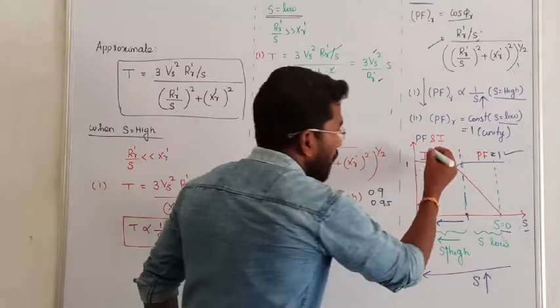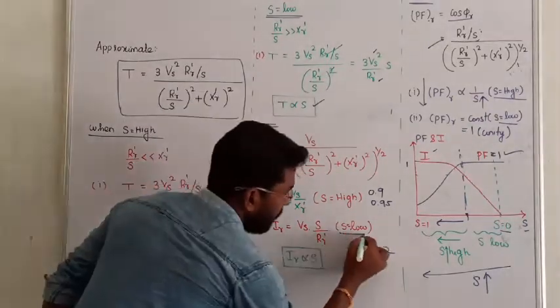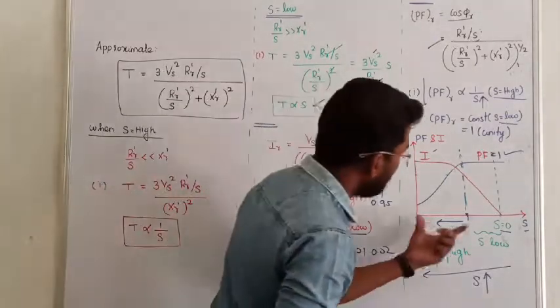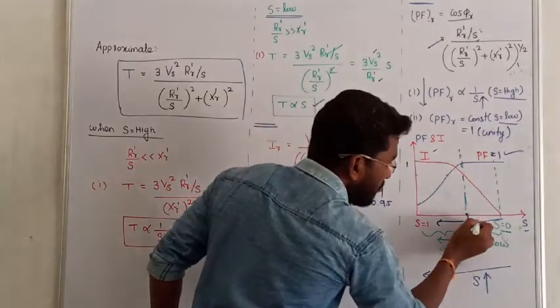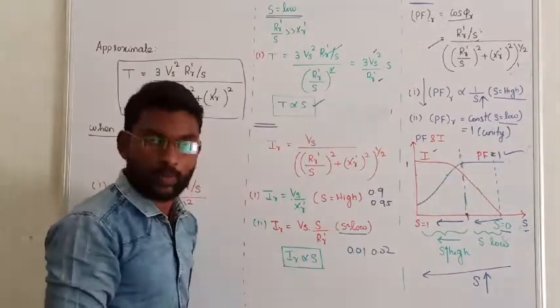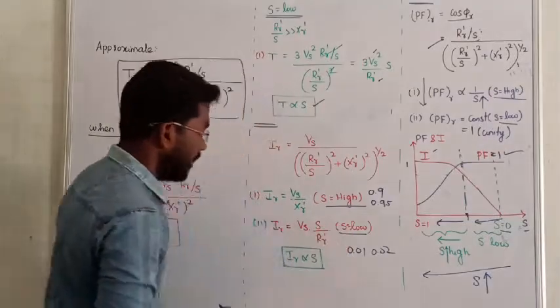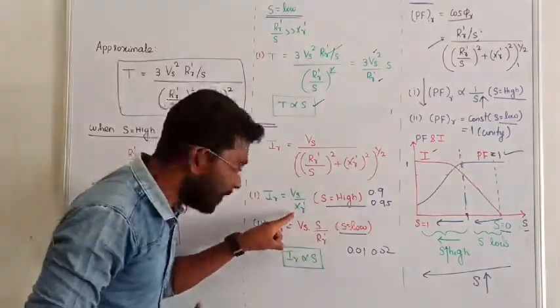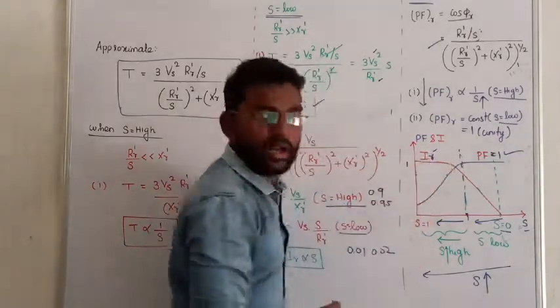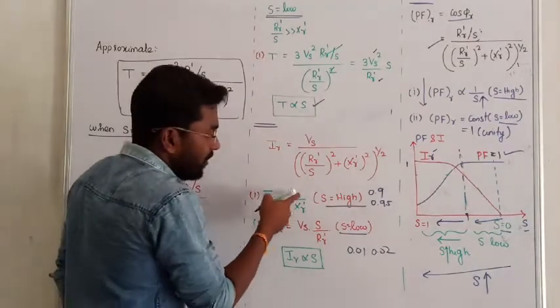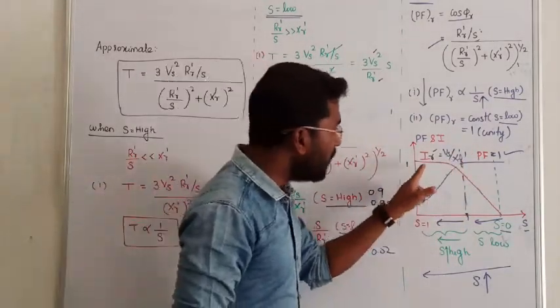Next: current versus slip, that is rotor current versus slip. From this observation, when slip is low, rotor current and slip are directly proportional. In the low slip zone, as slip value increases, rotor current increases. When slip becomes very high, rotor current will become independent of slip value — there is no change in the value of rotor current. It will be fixed at the constant value Vs divided by XR'. That is the characteristics of current versus slip.